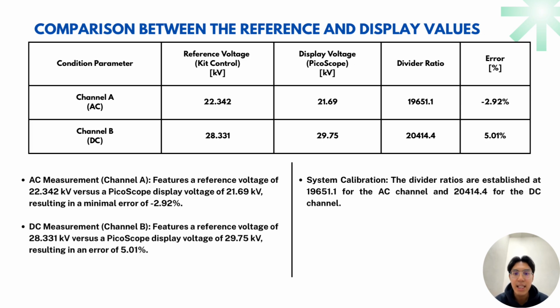at our AC and DC channels alongside their established divider ratios. For channel A, which handled the AC measurements, we recorded a reference voltage of 22.342 kilovolts against a PicoScope display voltage of 21.69 kilovolt. This presents a minor underestimation error of negative 2.92%. For channel B, our DC measurement channel, the reference was 28.331 kilovolt compared to a PicoScope reading of 29.75 kilovolt, which shows a slight overestimation error of 5.01%. Crucial to this setup are the divider ratios shown in the fourth column.